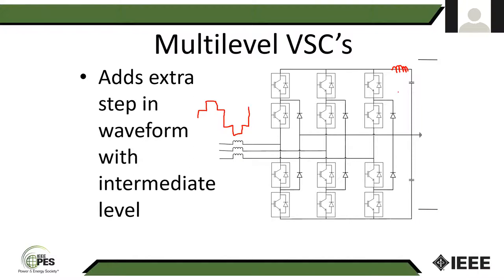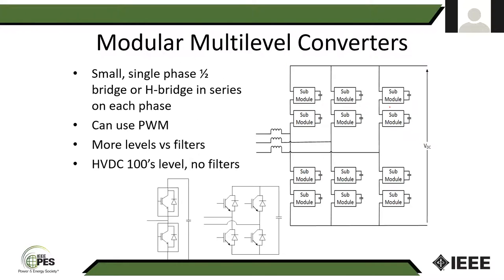Thank you, Dr. Johnson. The next question we have is, up to what extent in multi-level inverters is acceptable for microgrid application? And this is asking a question as a planning engineer, like a trade-off. So, I mean, if you're coming from the point of view of a power system owner, in a lot of ways, that decision is made more by the people who are buying the equipment and putting it in. And so the question on that is really coming down to where the converter manufacturers are deciding the optimal module size. So the big advantage of modular multi-level converters is having these standardized modules you can mass produce.